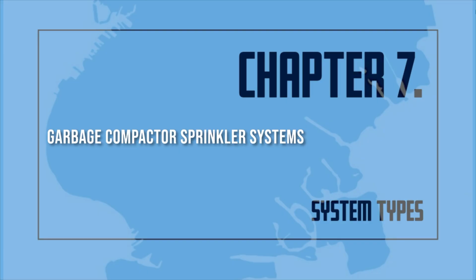The certificate of fitness holder may be questioned about this sketch by inspectors from the fire department during routine inspections. A sign indicating the location of all control valves shall be kept in the compactor room. This sign shall be displayed with the sketch in the compactor room. All control valves in the sprinkler system shall be labeled. The label is to show the purpose of the valve. Additionally, the labels shall be attached to the yoke of the valves.